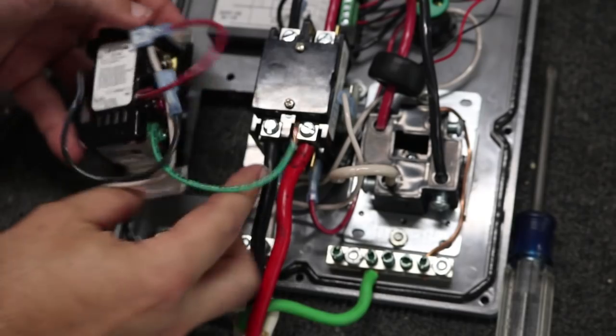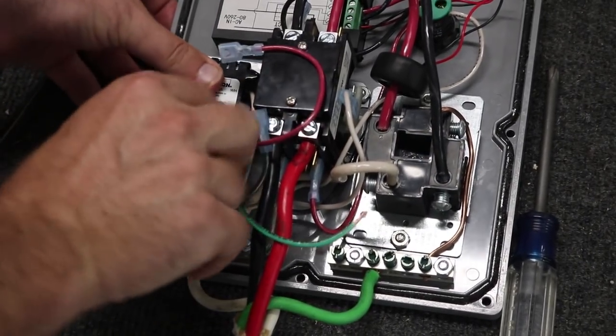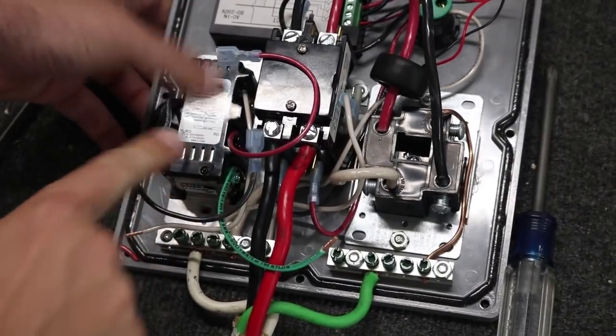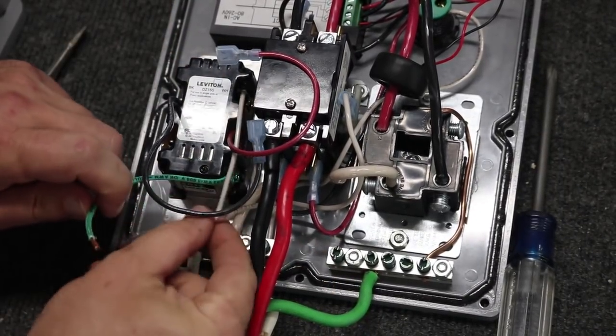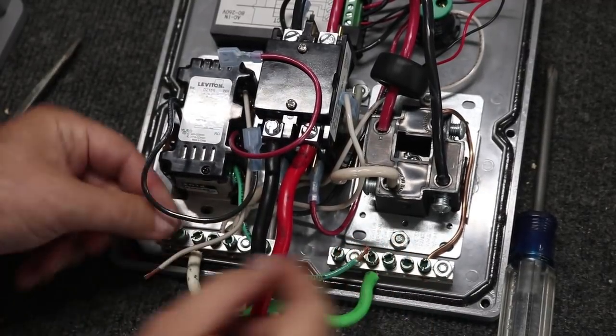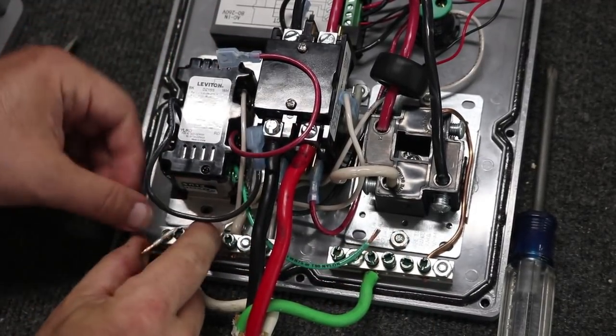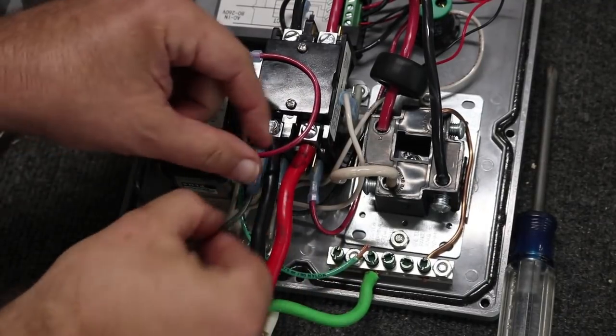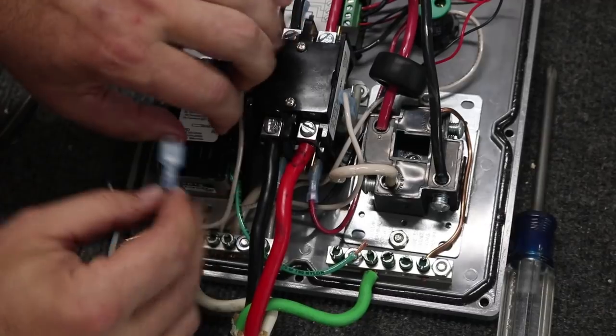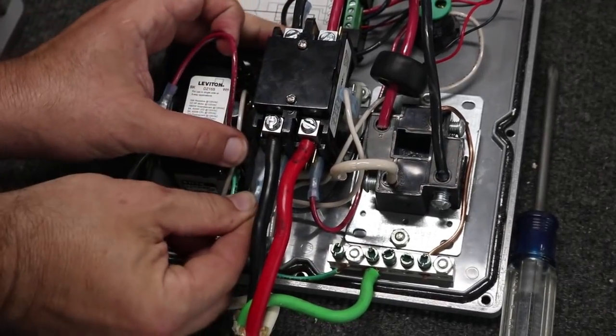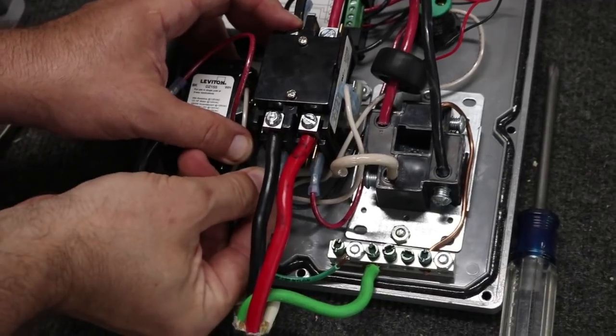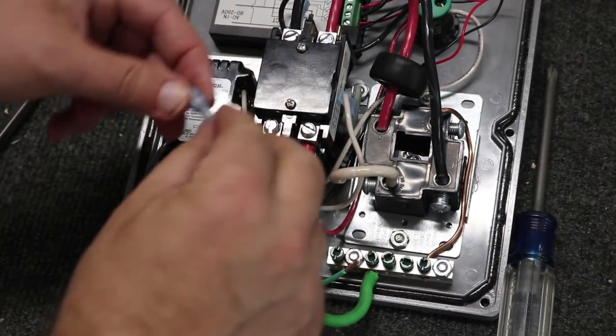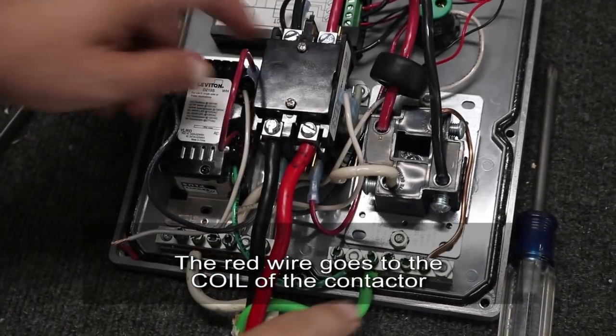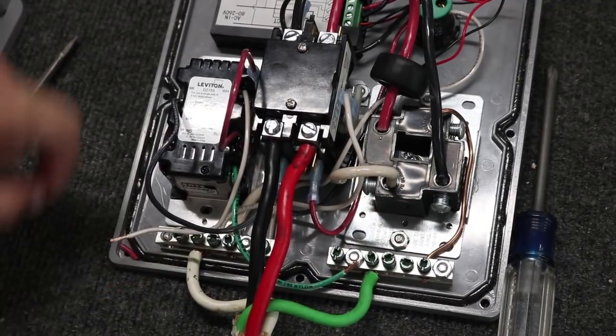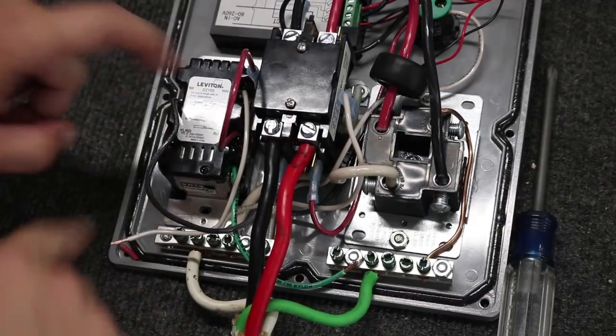And then if I pop the switch down into place here, the green ground wire is going to go right over to the ground bus. The white neutral wire is going to come down here to the neutral bus. The black hot wire is going to connect to one of these spade connectors right down under the hot. I'll put that on, push that in. The red switched hot is going to the contactor. So I'll make the ground and neutral connections, put the screws in to hold in the switch, and then I should be able to test this.